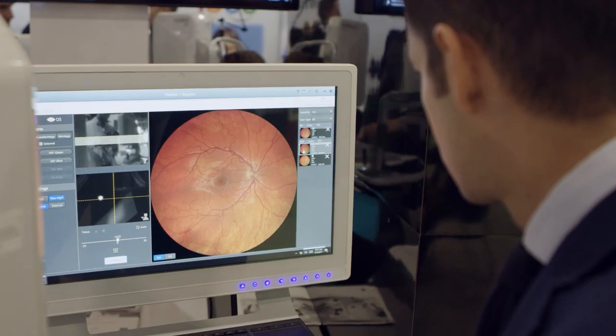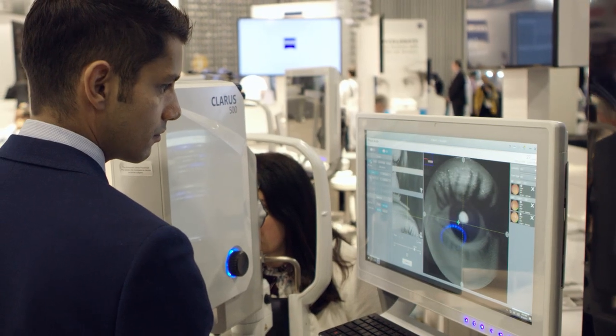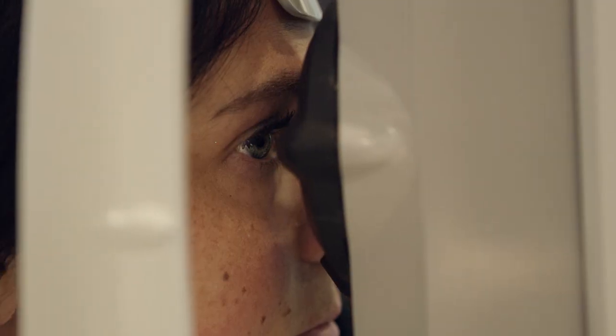One thing I really like about the CLARUS system is that there's a live feed while you're taking the image, so you're really able to see the retina and focus on it. If you need to look at a particular lesion, you can quickly change fixation and go to that retinal location. Because you have a live feed, you can see if it's in focus or out of focus — you don't need to take 10 or 15 images to get one good one.